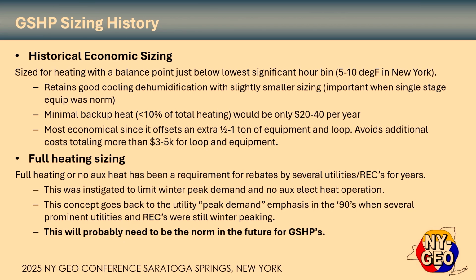Full heating sizing came about primarily in the mid-90s when a lot of the rural electrics were worried about peak demand more, and they had a fairly substantial rebate. You could get $1,000 or $2,000 sometimes per ton even, and if you did that, then they wanted you to have a piece of equipment that did not require what I'm going to term auxiliary heat, that is electric heat that would turn on with the heat pump to do that supplemental little triangle on the top. And in order to do that, you had to size equipment slightly bigger to get that balance point down low. And of course, those rural electrics have done that really for 20 plus years now, and so that's very common.